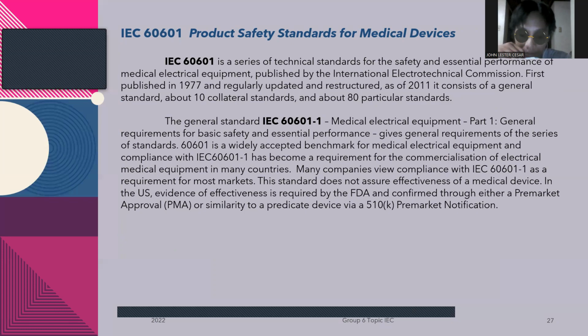Next is the 60601 Product Safety Standards for Medical Devices. IEC 60601 is a series of technical standards for the safety and essential performance of medical electrical equipment, published by the International Electrotechnical Commission. First published in 1977 and regularly updated and restructured as of 2011. It consists of a general standard, about 10 collateral standards, and about 80 particular standards.